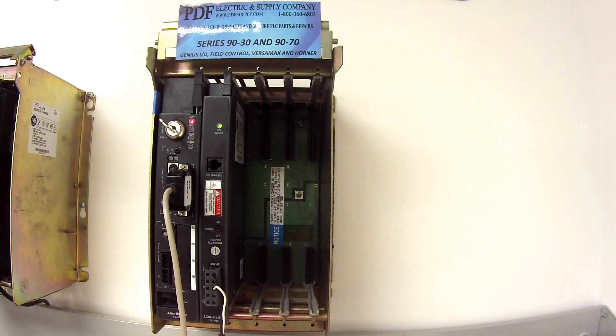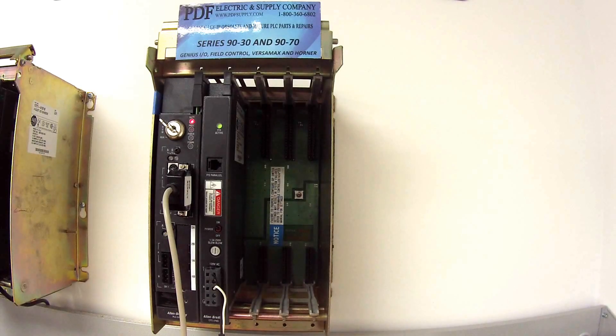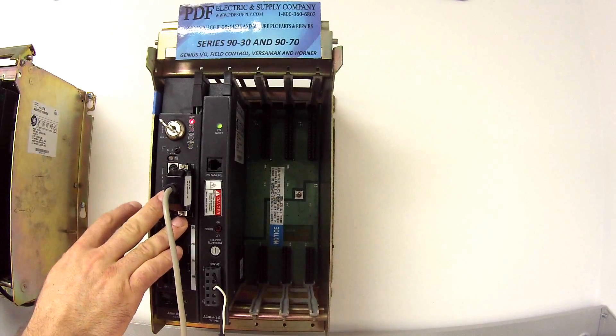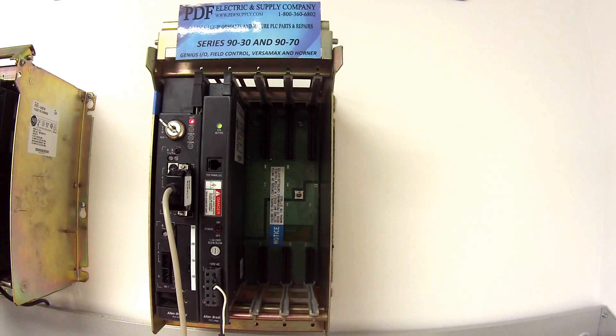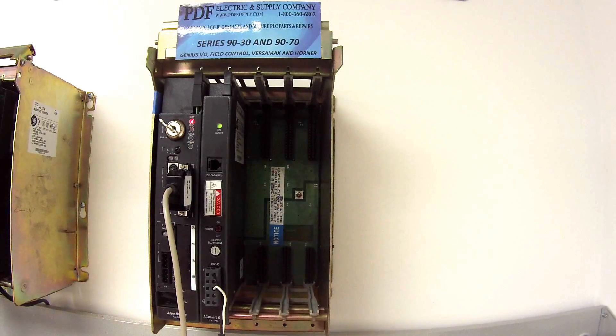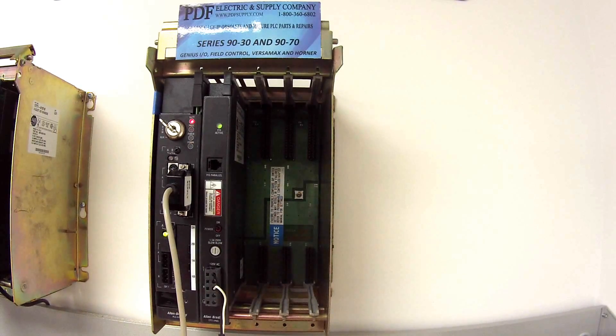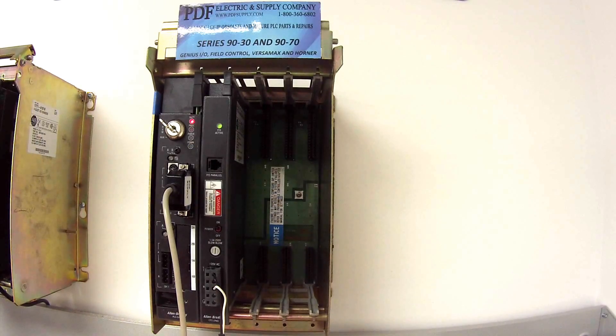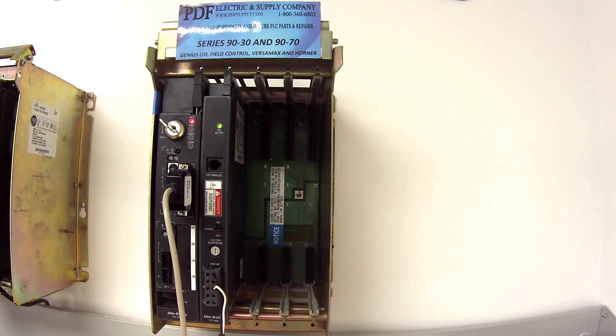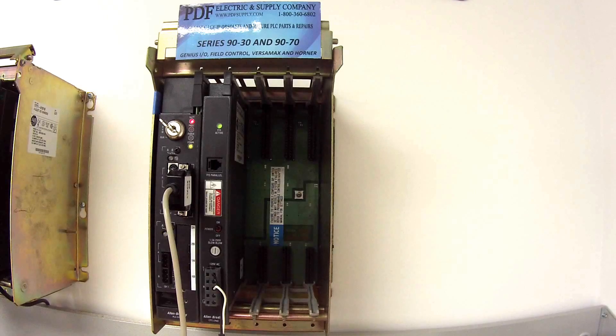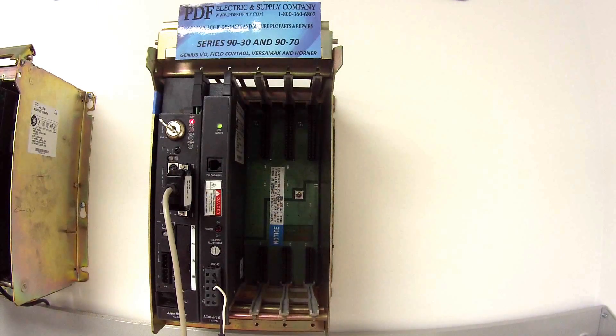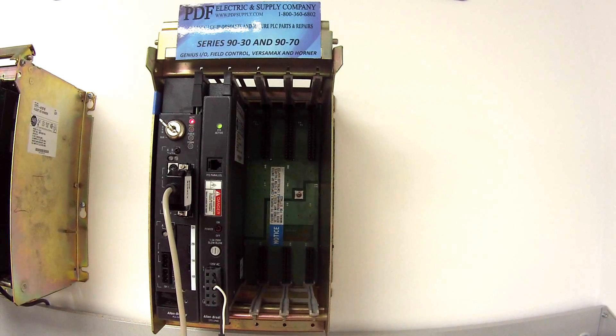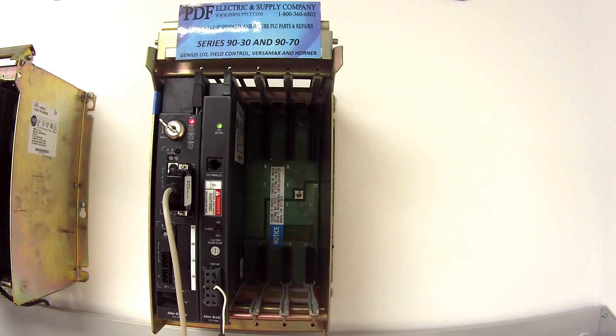And here's a point where you can make some changes. For this particular test, I'm going to leave the configuration of the channel at 2400 baud, which is kind of slow. If you decide that you want to communicate at a faster rate, you can open up channel configuration in the left-hand side. Edit channel properties, window will pop open, channel zero. If you go to serial port, baud rate, there's a drop down menu that allows you to communicate up to 19,200 baud, 19.2k. And if you choose, you can select that, communicate faster. But again, for this test, I'm just going to communicate at the 2400 default.